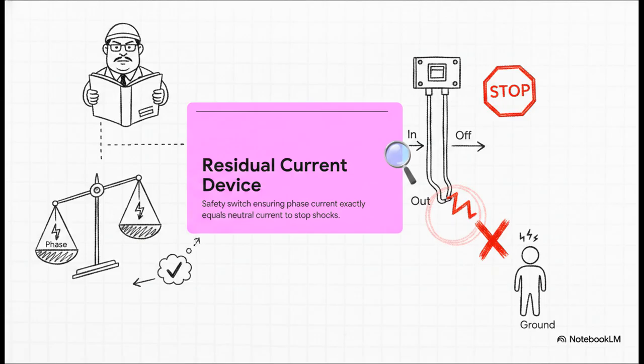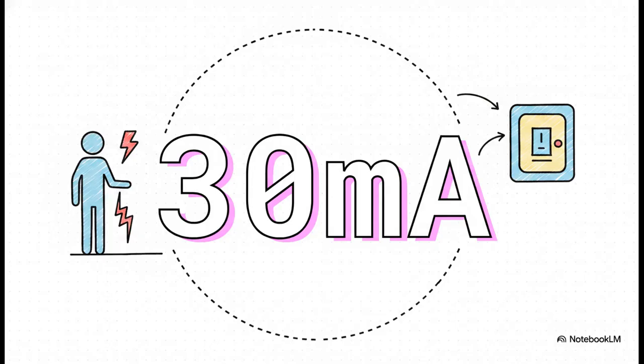The electricity flowing into your house on the phase wire absolutely must equal the electricity flowing back out on the neutral wire. If this accountant sees that the current going in doesn't perfectly match what's coming back out, it knows there's a residual current, basically a leak somewhere. And a leak usually means the current is finding some different path to the ground, which is a massive, massive hazard.